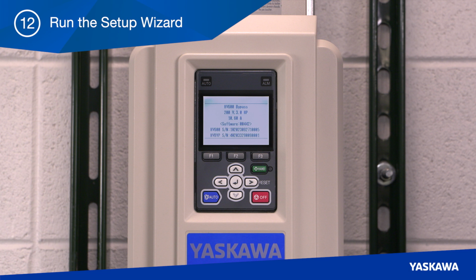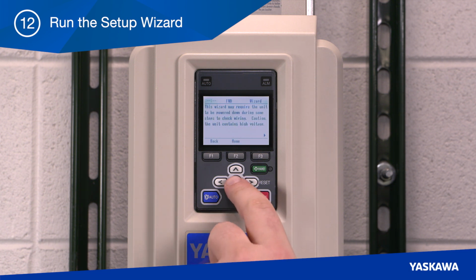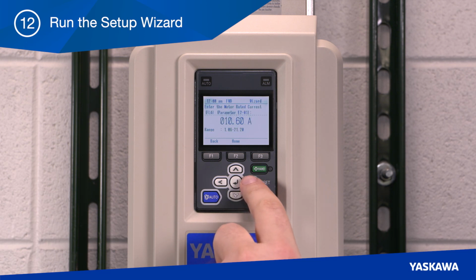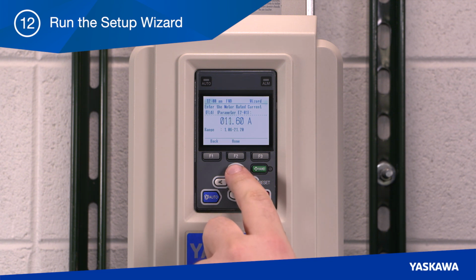At Step 12, run the Setup Wizard. If this is your first time starting up the bypass, push Enter and run the Setup Wizard. You will be asked to set the date and time. You will then be asked to set the motor-rated current parameter. This step is essential for bypass startup.